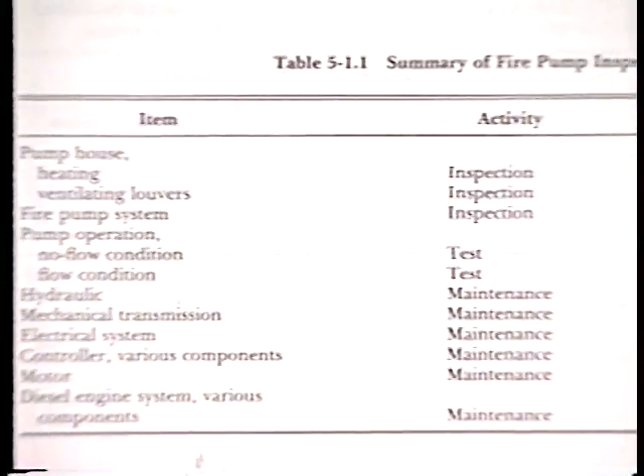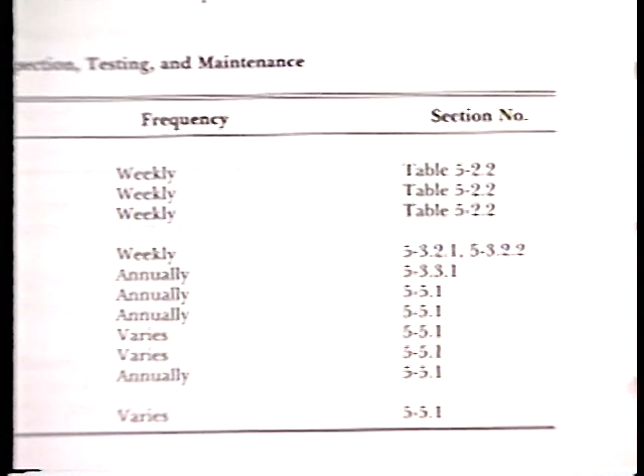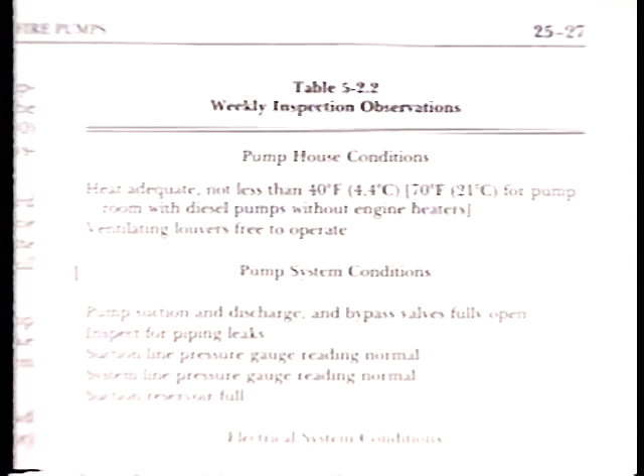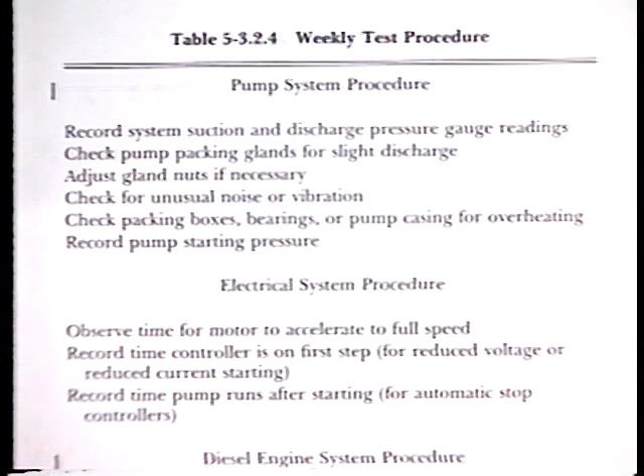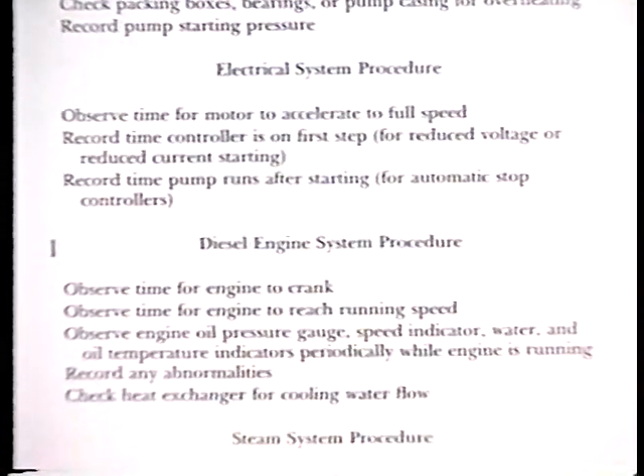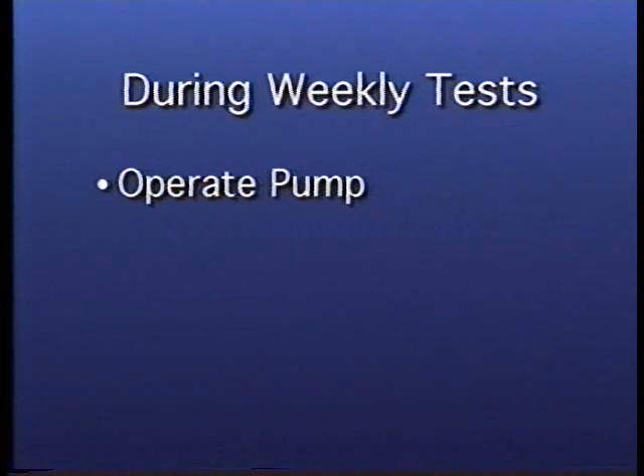Here we've summarized the inspection, testing, and maintenance of fire pumps, which can be found in Table 5-1.1 of NFPA 25. The inspections are further described in Table 5-2.2. These inspections are intended to determine that the pump is in operating condition and not damaged in any way. The weekly and annual test procedures are further described in 2 more tables, Table 5-3.2.4 and Table 5-3.3.2. During the weekly tests, the pump is to be operated. It is permissible to test under no flow conditions.